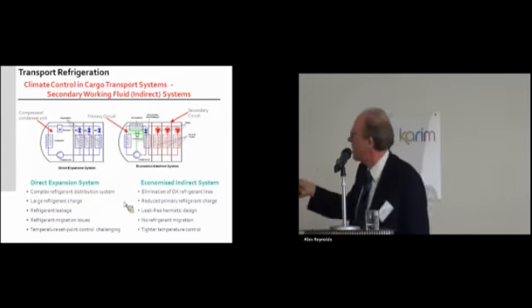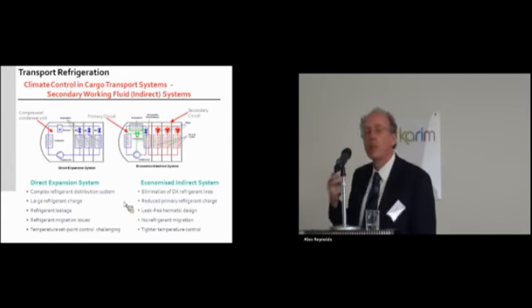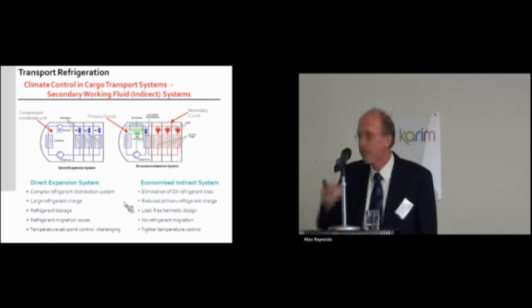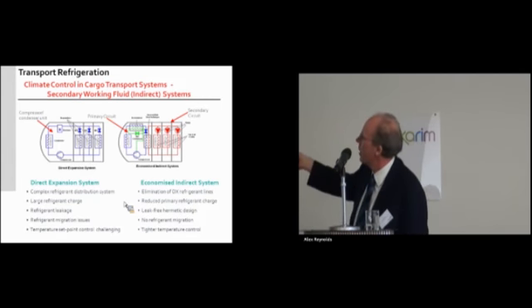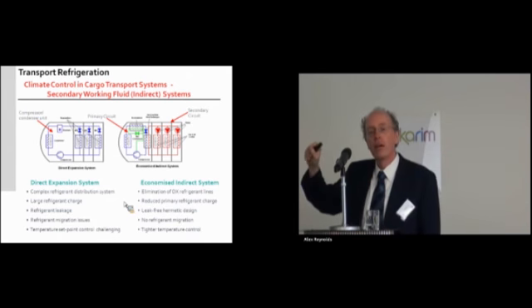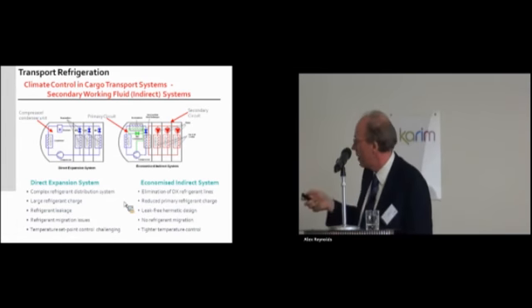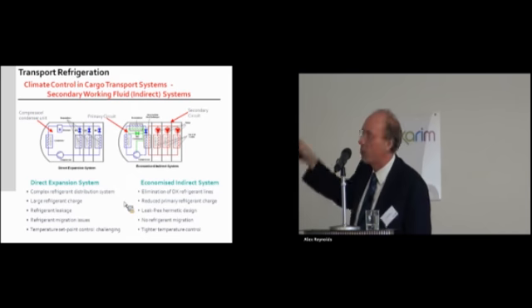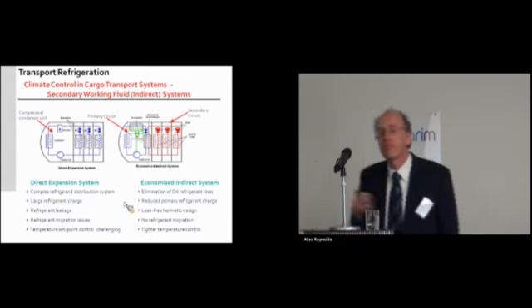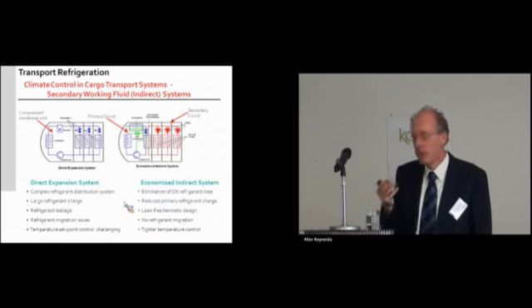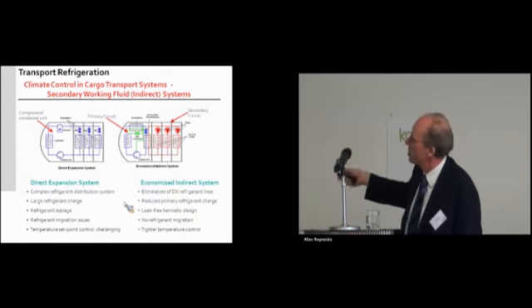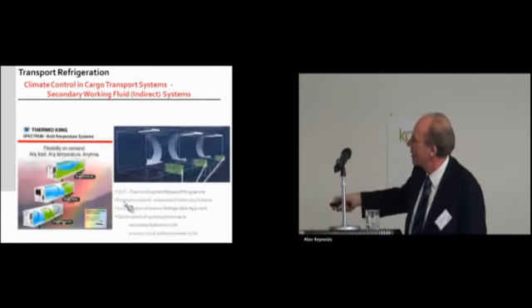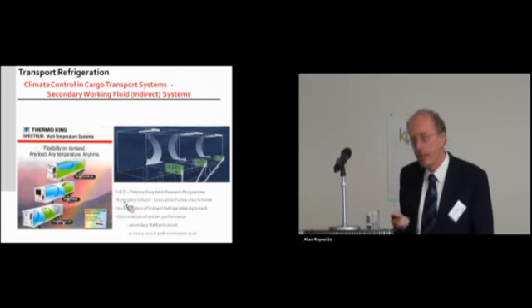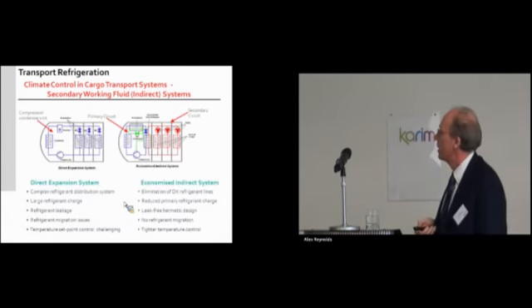So what we're looking at here is using what we call a secondary working fluid, something like an antifreeze, used for the cooling in the containers itself. This gives a much reduced primary circuit, with the charge reduced from about 15 to approximately 2 kilograms. The other advantage is that the charge is now all contained within the front unit in the truck, so there's much less chance of damage during operation, and a reduction in leakage.